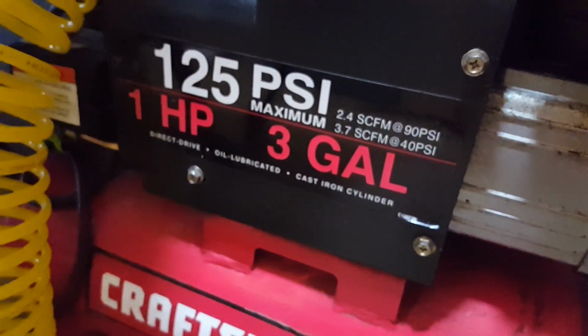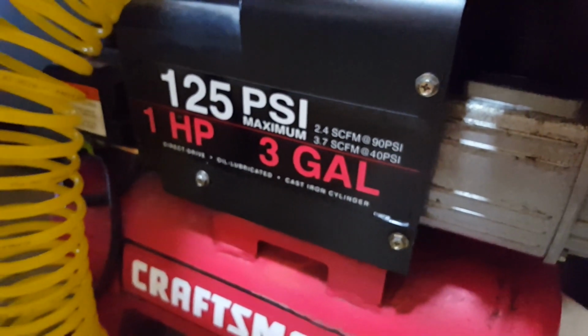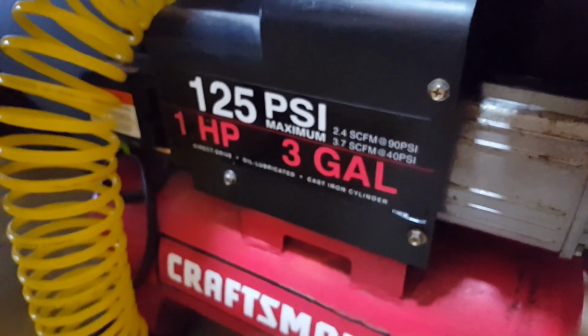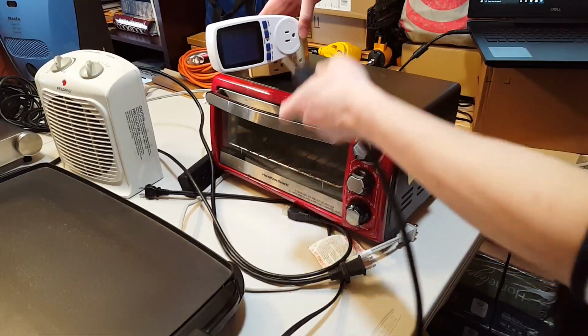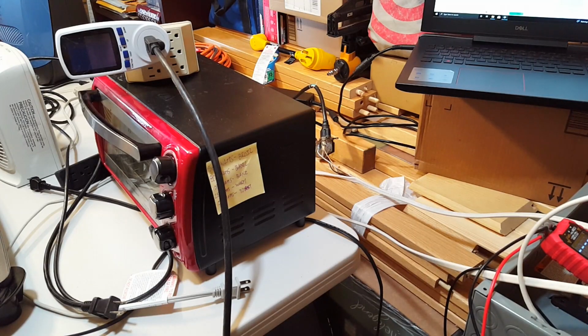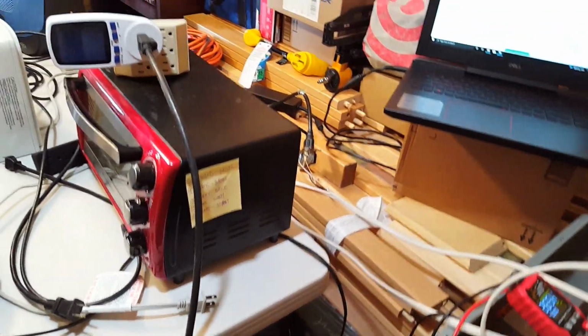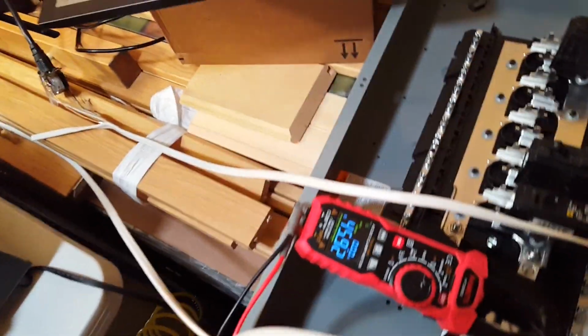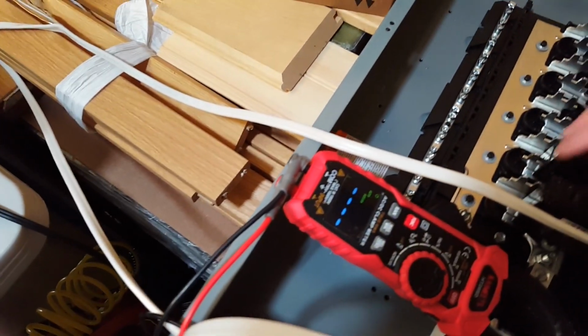The next thing I want to do is this air compressor down here. This is a 1 horsepower, 3 gallon. Check running amps, AC and DC, and we'll look at the surge amps, AC and DC as well. Okay, starting compressor for AC inrush test. That inrush is 45.92 AC amps inrush. One more time. So, inrush test.